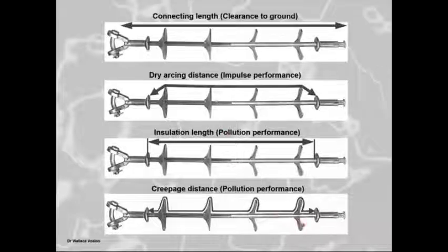And then last but not least is something called creepage distance. And obviously that influences your pollution performance quite significantly. But the creepage distance is the shortest distance where you go from metal to metal over the surface of the insulator. So here you can see walking over the surface of the insulator, and the ant walking over the surface taking the shortest distance would be your creepage distance.